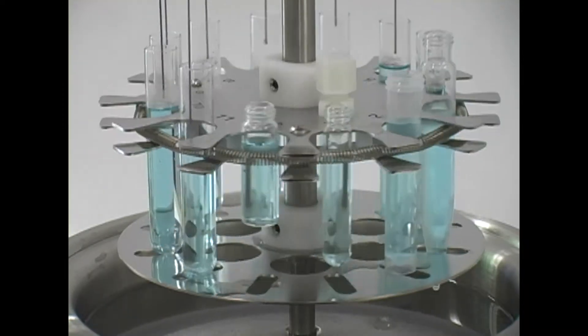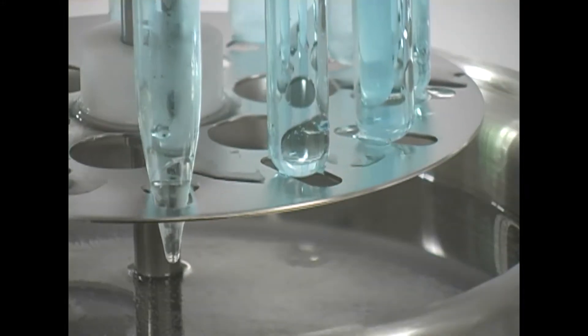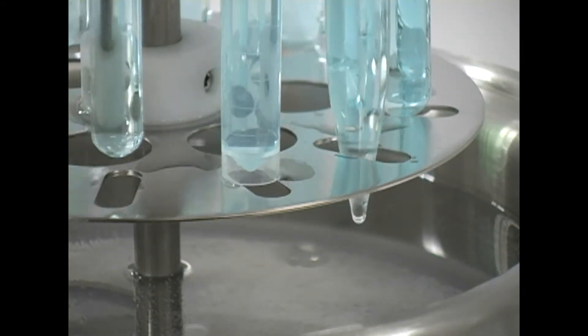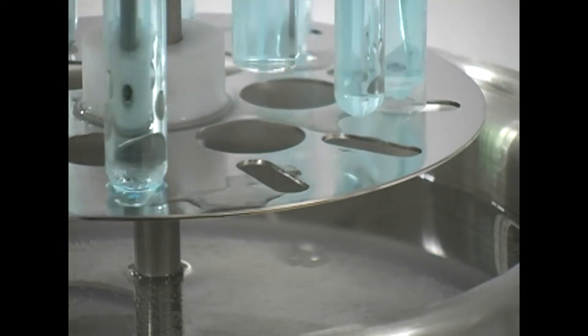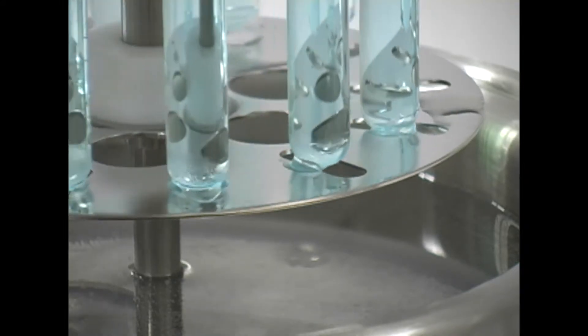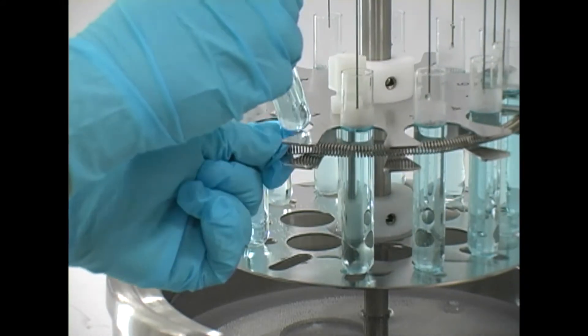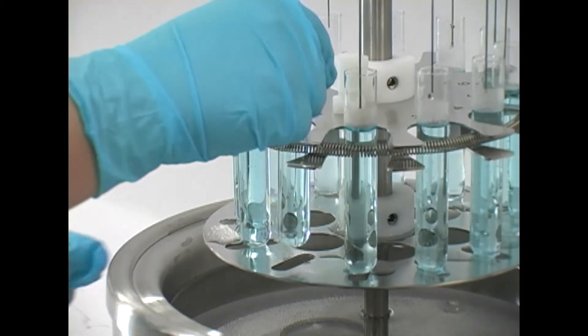Flexibility sets the N-EVAP apart from other evaporators. Our unique sample holder is able to accommodate a wide variety of popular vial sizes without additional racks or accessories. An adjustable spring design holds each vial securely in place during evaporation.